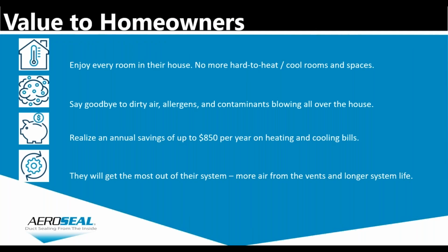So a few value points here for homeowners. They're going to enjoy every room in their house. It evens out the delivery of conditioned air, so there are no more hard to heat or cool rooms and spaces. Secondly, on the air quality side, it greatly reduces the deposition of dust all over the home. Sealing the returns gets the contaminants into the filter media where we hope to have them go. The first thing homeowners recognize is the comfort, which is why we put that bullet point number one. The second thing they notice is they don't have to dust as much.